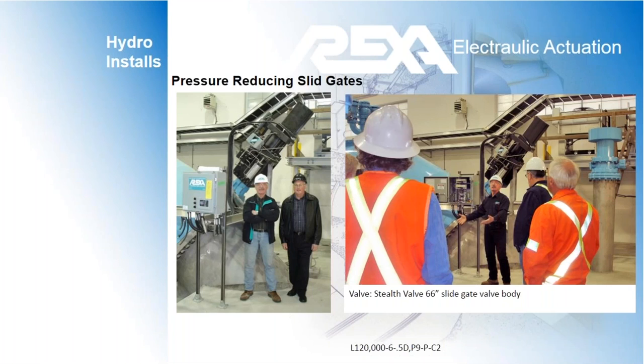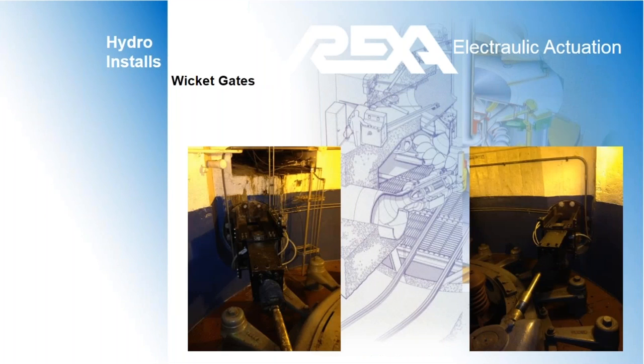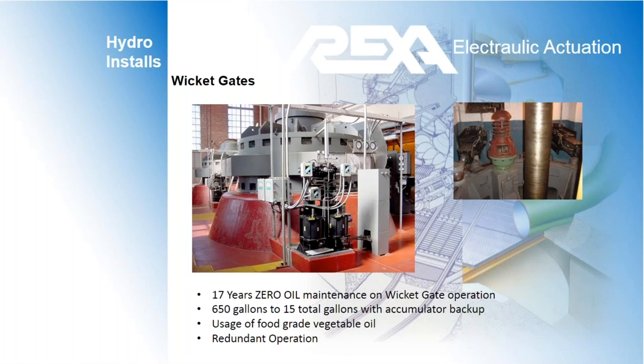On this slide, there are two REXA actuators operating pressure-reducing slide gates. These are high-force actuators with a 6-inch stroke, capable of generating 120,000 pounds of linear force. REXA has extensive experience on turbine control in the power industry. In this picture, the REXA operates wicket gates that use a double piston design where the cylinder moves in tandem. Cylinders in the pit are mounted via mid-pivot, and hydraulic lines are linked to the REXA skid, accessible to operators at the turbine deck.